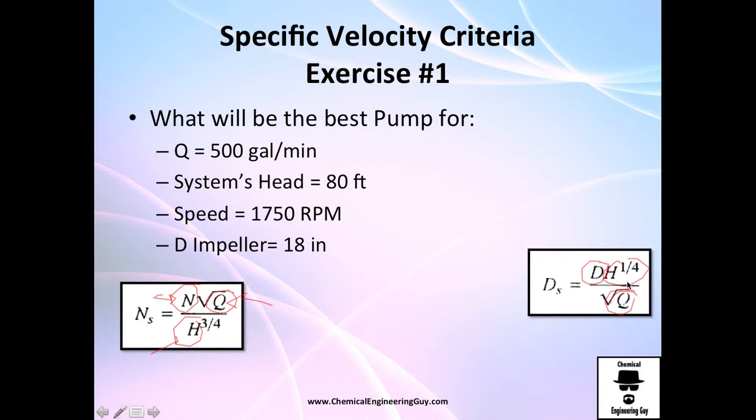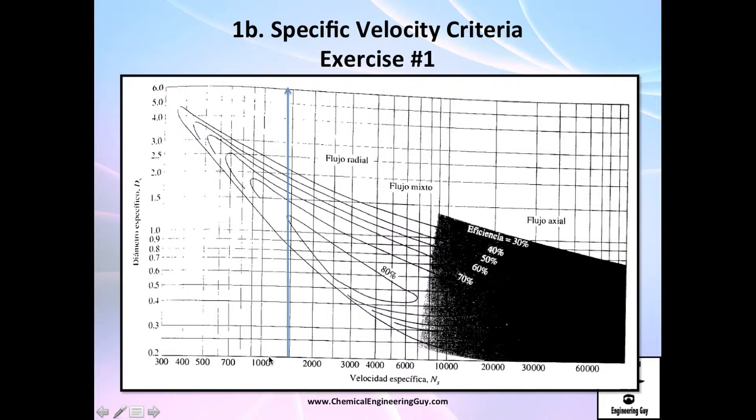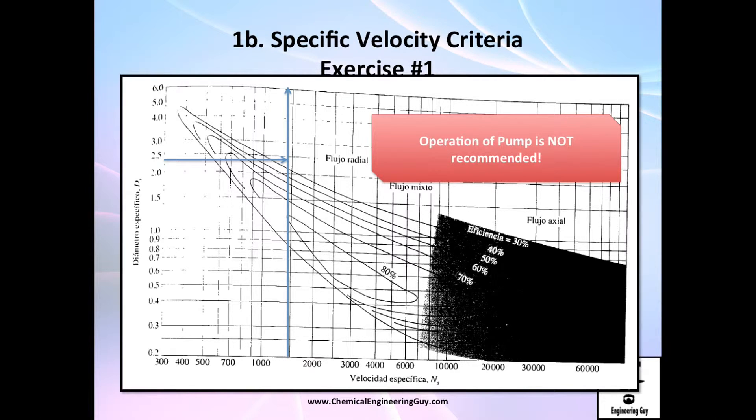So doing this, I got these revolutions per minute, this head and this volumetric flow rate. I got this specific velocity. The same for diameter. Let's go back to the graph. This is my specific velocity and this is my specific diameter. As you can see, the point is out of the normal operation. If this line is 30%, I could say this is between 20% and even 10%. So this is pretty bad operation. This is not recommended to operate.